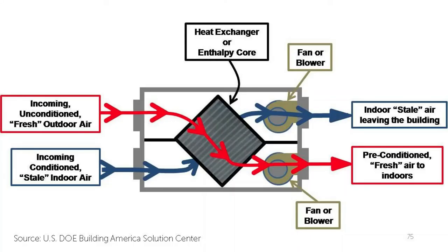Heat recovery and energy recovery ventilators can provide balanced whole house ventilation while preconditioning the incoming air using the exhaust airstream. If viruses and other microbes are a concern, HRV and ERV specifications will need to be reviewed for cross-contamination potential in airstreams and heat or energy recovery materials. Energy recovery ventilators transfer heat and moisture from the exhaust airstream to the incoming airstream. This can be helpful in maintaining comfortable indoor relative humidity levels in the winter in dry Vermont homes, but can also pose a risk if surfaces in that home are below the dew point, such as a cold window. If you're not sure whether a HRV or ERV would be best, get one with a swappable core for easy modification should the first one you select not work out.